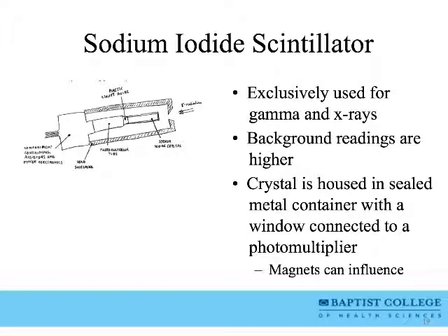All you need to know about this is that it is not operating like a Geiger counter. It is using scintillation. So sodium iodide crystals are forming light, and that's what's being read. So if you notice, it has sodium iodide, a photomultiplier, and then a way of reading that out. And you're going to see all that stuff again when we talk about digital X-ray.